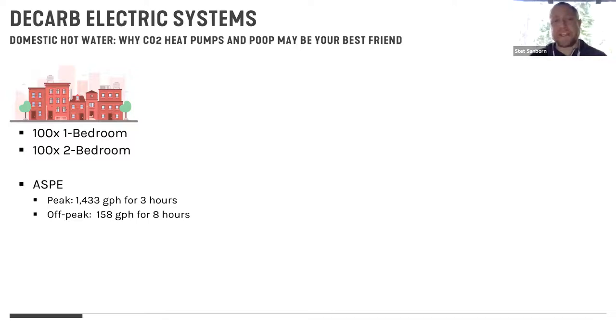At each building, they do have a little bit of dehumidification demand that's particular to the experiments that are happening. And so that's done with essentially a boost heat pump that takes the 55 degree water and bumps it down to the temperature that they need for chilled water. So it's not really a condenser water shared loop, although in most climate zones, that would make sense.